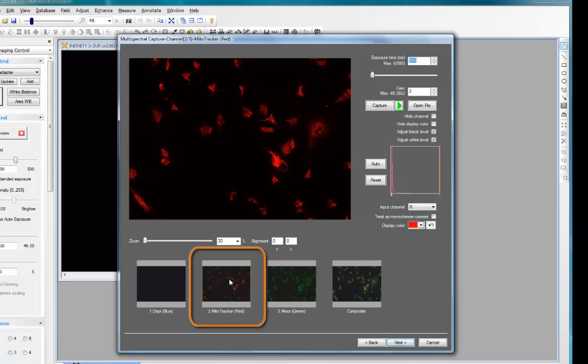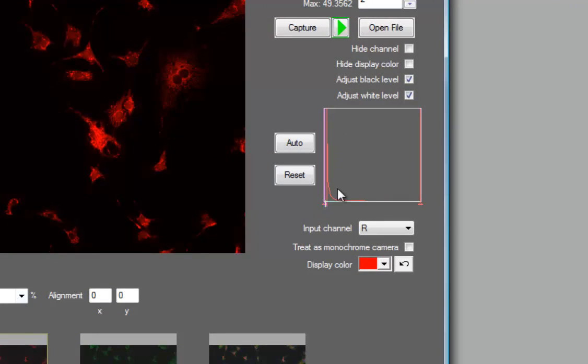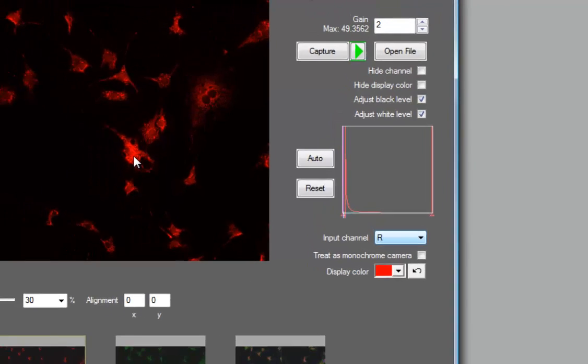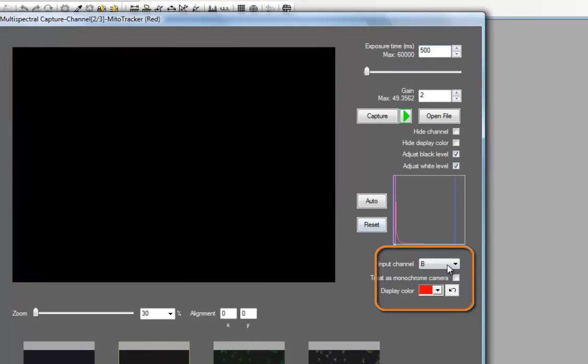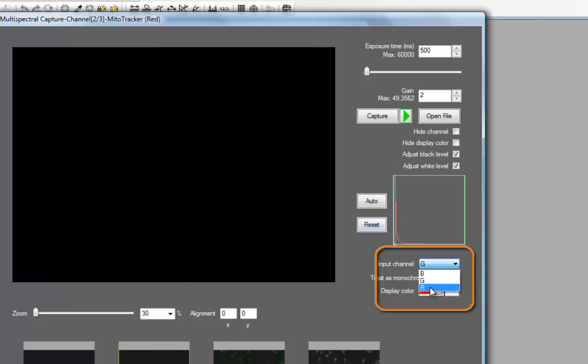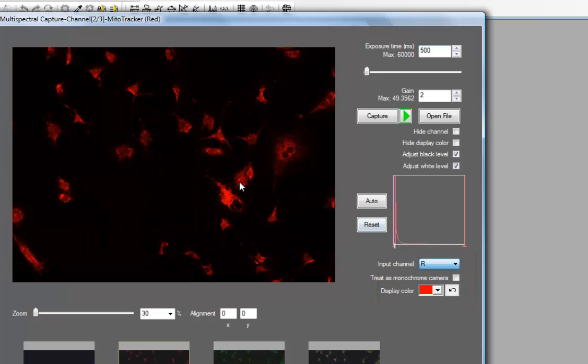By clicking on the MitoTracker red thumbnail, I can take a look at this channel, and I see a distribution histogram showing me what the output looks like from that image. We're talking about capturing from a color camera. In this instance, I have my input channel set to red, because the dye that I'm using in the filter cube is actually outputting a red color. You'll notice that if I were to have my channel selector set to blue from this color camera, or set to green, there is really no emissions in the blue or green areas of the spectrum, so my camera does not see the channel output as produced through the filter cube. So for that reason, it's important to make sure that your input channel has been correctly specified to match the output colors.